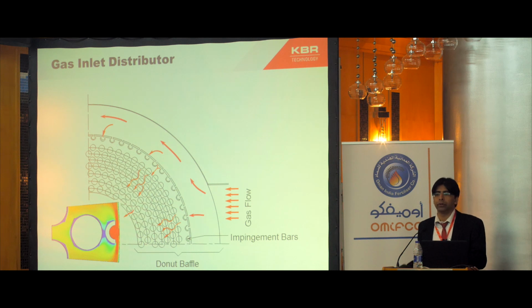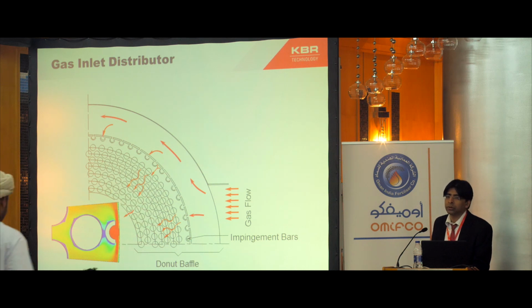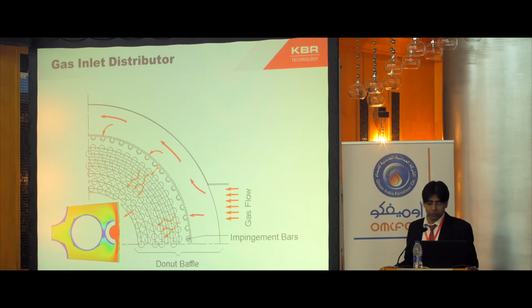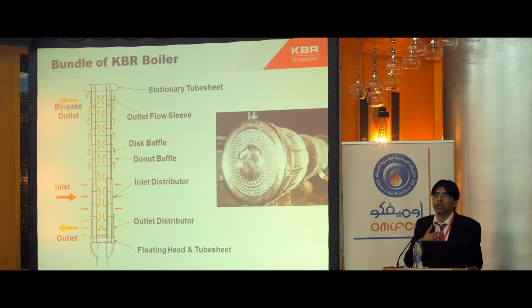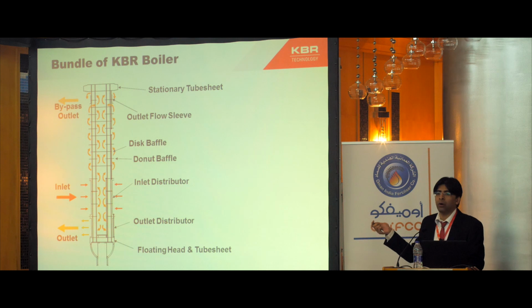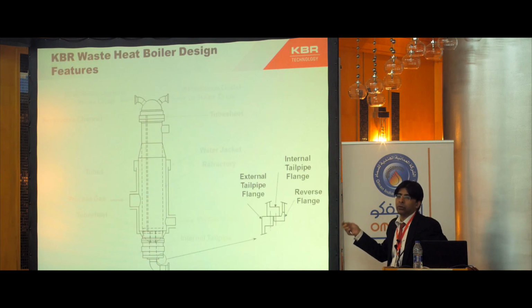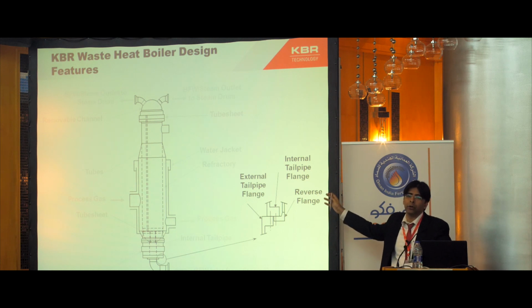Any more questions? Well, I want to discuss the way of removing the bundle from this boiler, because people probably suffer from the shroud being distorted and damaged. Then you will have a problem pulling out the bundle itself. So you're talking about the metal liner which was used in earlier designs. Now there is no metal liner. The only thing is there is dual layer refractory. So there is no metal liner which will get out of shape. You can easily remove the bundle in 3 to 5 days.